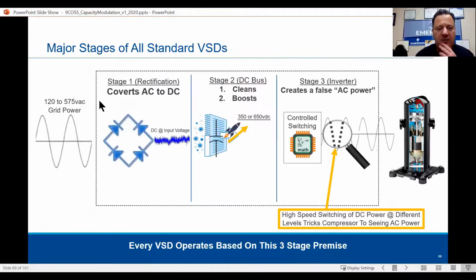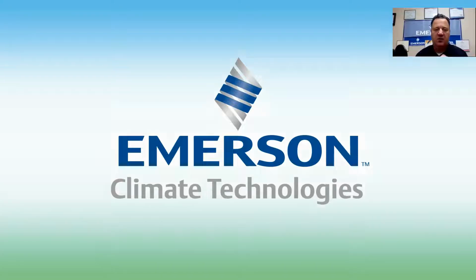One last time with a little bit of animation. Stage 1, rectification, converts AC to DC. Stage 2, DC bus. It cleans it and it boosts it from 350 or 650 VDC, okay? Stage 3 is the inverter. It creates a false AC power, high-speed switching of DC power at different levels, tricks the compressor to see AC power. And that's what it's doing, okay? The gates. Every VSD operates based on this three-stage premise. Let's see if we watch this video, if it helps out a little bit.